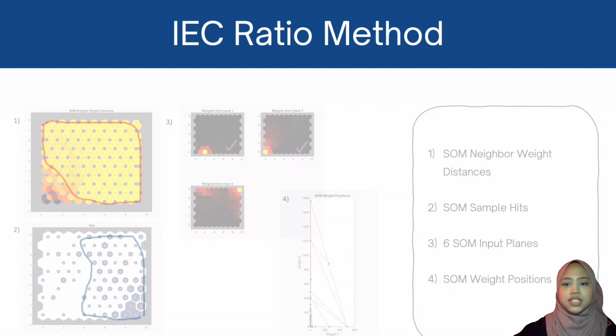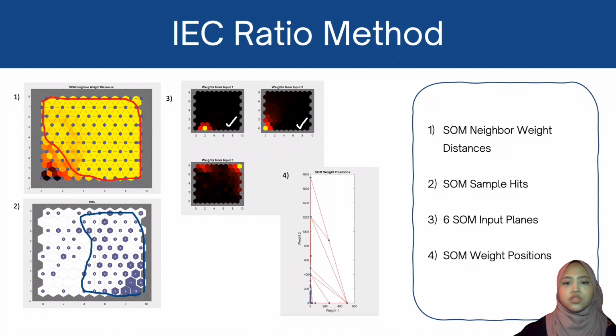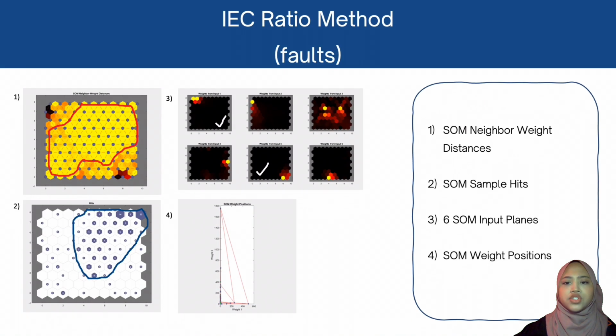For the IEC ratio method. For IEC ratio analysis, SOM input planes show similarity between input 1 and input 2. Based on the SOM sample hits, the weights are more on the right side of the map. From fault analysis, SOM input planes show that the results of input 1 and input 5 correlate with the weight on the SOM neighborhood weight distance. It can be seen on SOM sample hits that the weights are more prominent on the upper right, which concludes that the fault's outcome is quite unclear to observe.